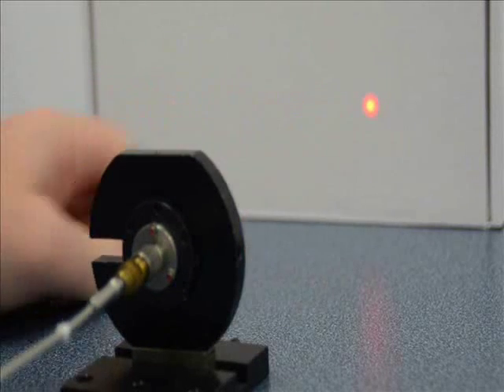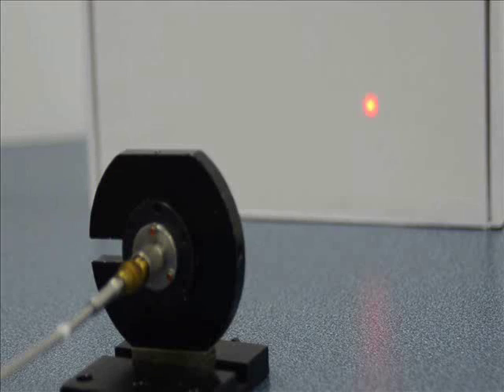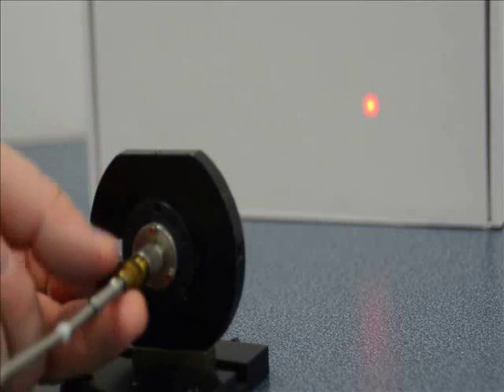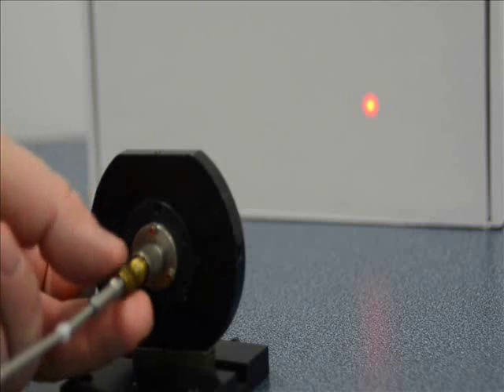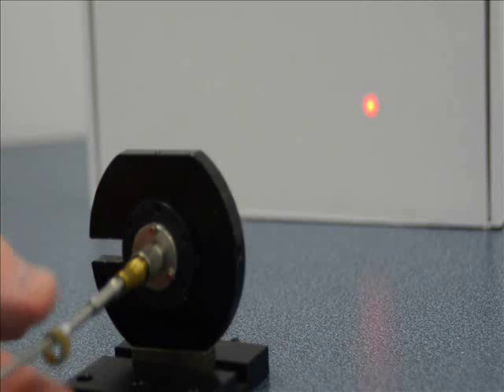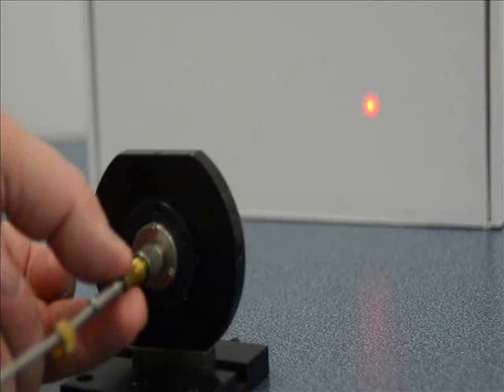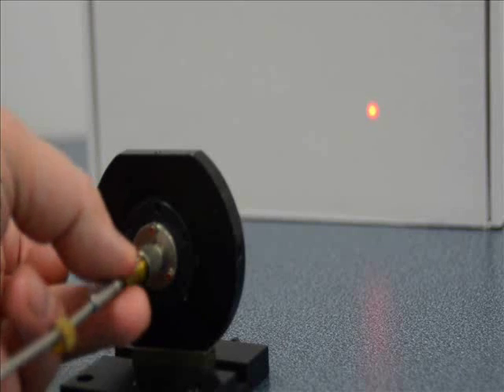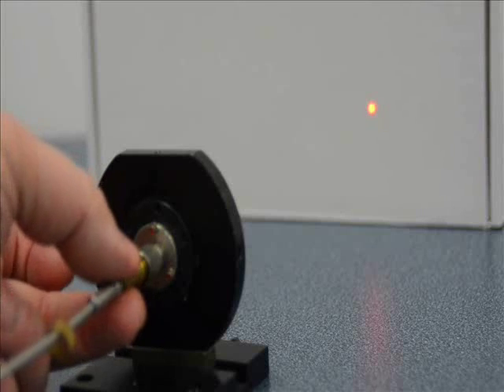And right now we have a fairly large beam on our screen. Once we loosen our locking nut, move it out of the way, we can adjust the focus here, and as I turn it, you can see how the beam is getting smaller and smaller, and we can generate quite a small spot on our screen.